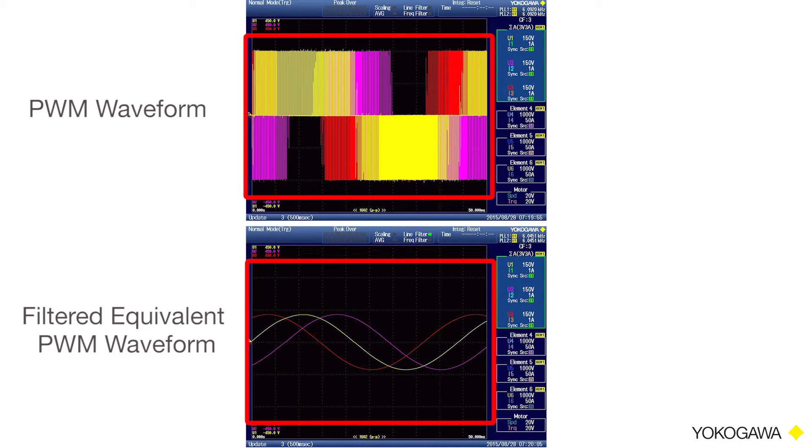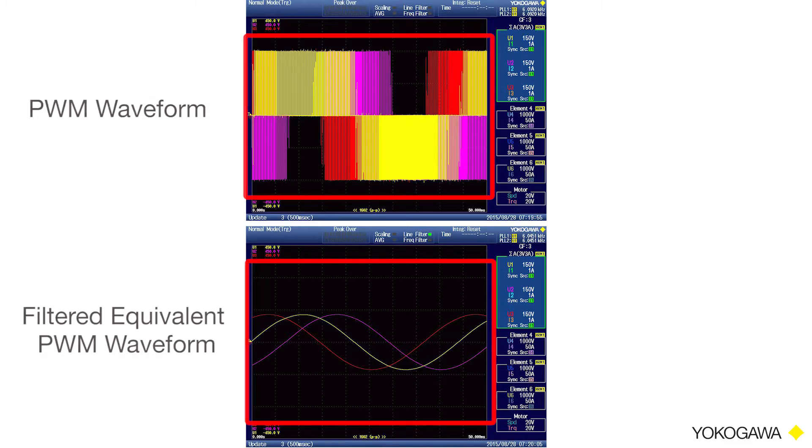On Yokogawa's power analyzers, this fundamental frequency is used to measure the RMS values of voltage, current, and power using integer number of cycles. This gives you accurate power measurements.